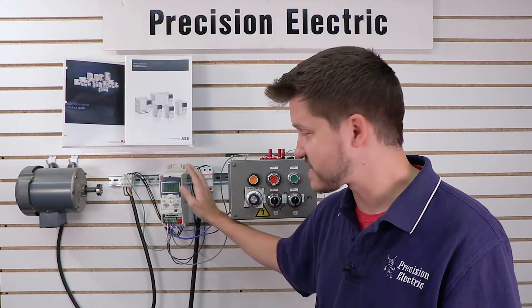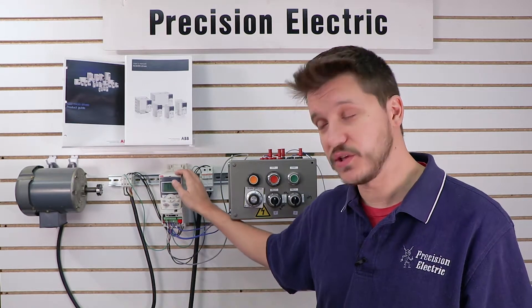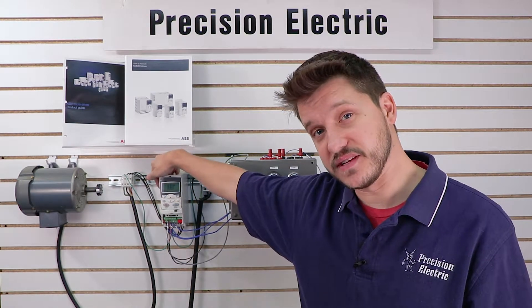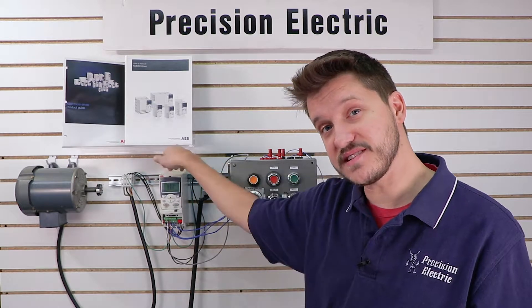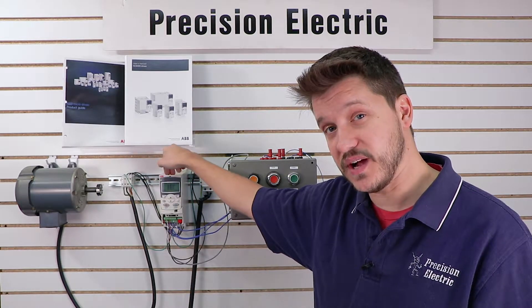If you had a three phase drive, then you would have three fuses that were actually protecting the drive. Now, in order to size the fusing on this drive, you want to look on the nameplate on the side of this. In my case, this is a 6.1 amp input drive.